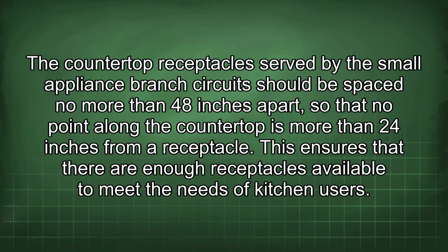The countertop receptacles served by the small appliance branch circuit should be spaced no more than 48 inches apart, so that no point along the countertop is more than 24 inches from a receptacle. This ensures that there are enough receptacles available to meet the needs of kitchen users.